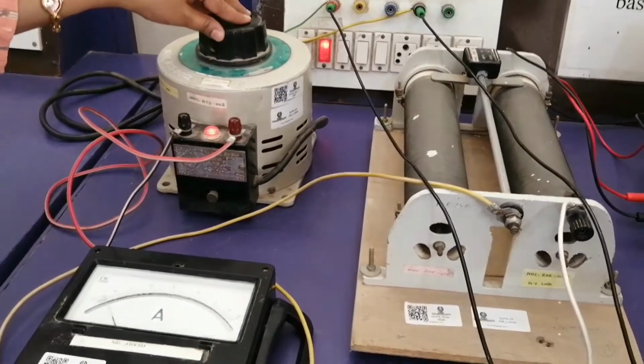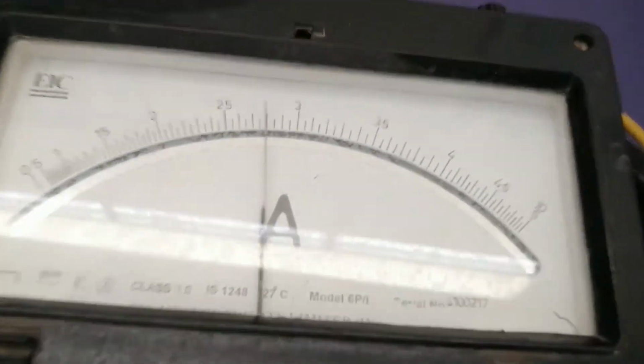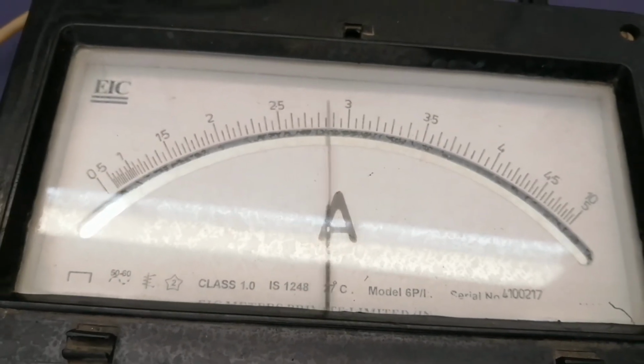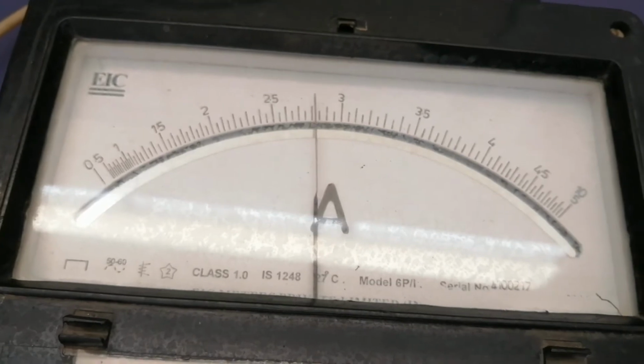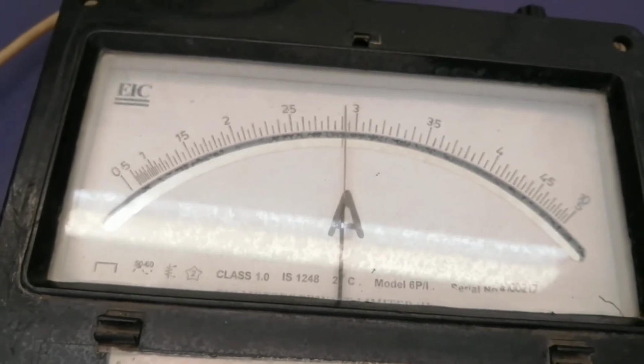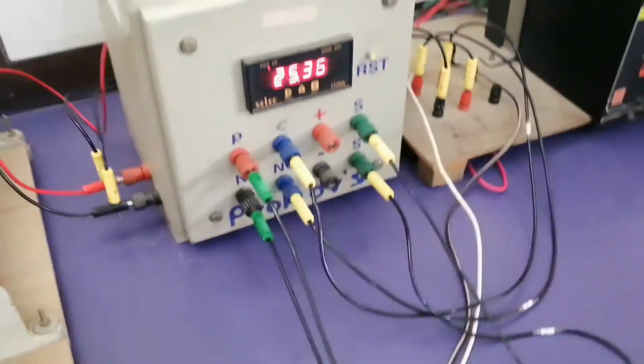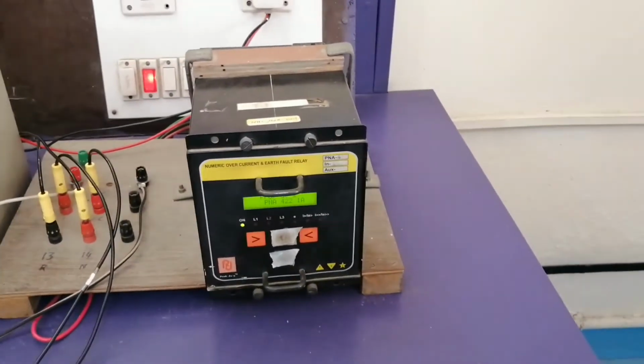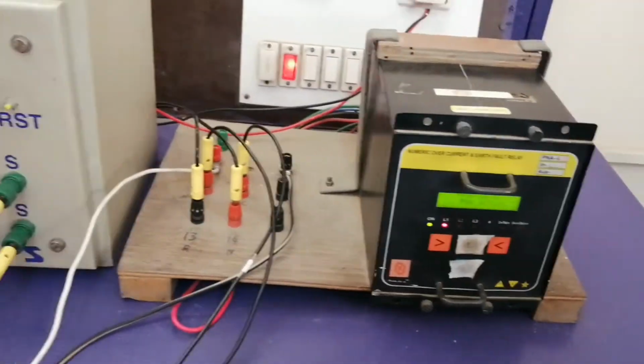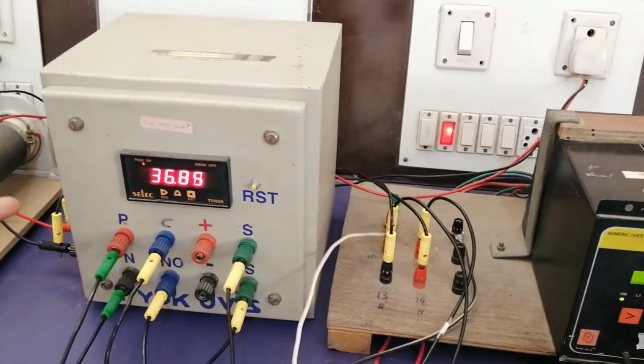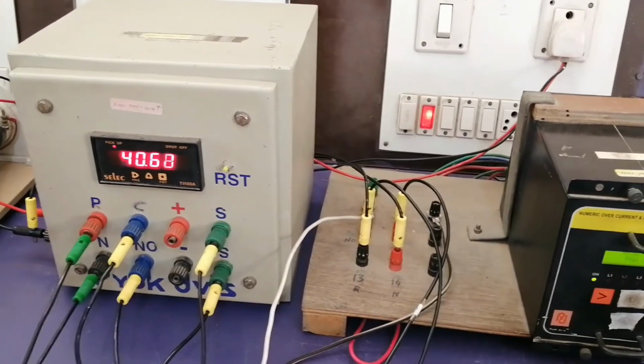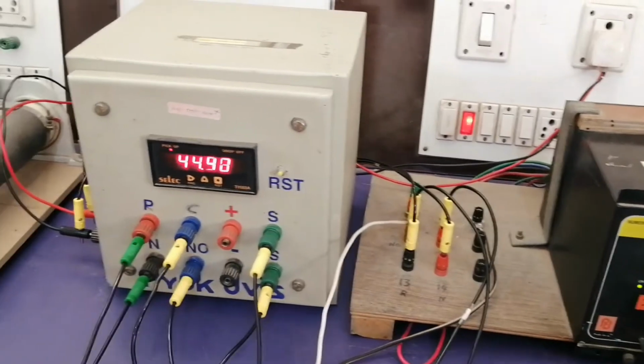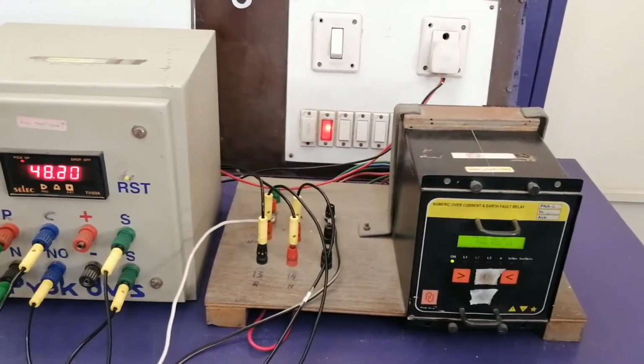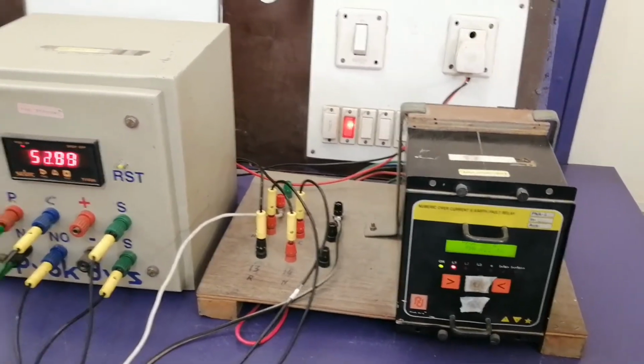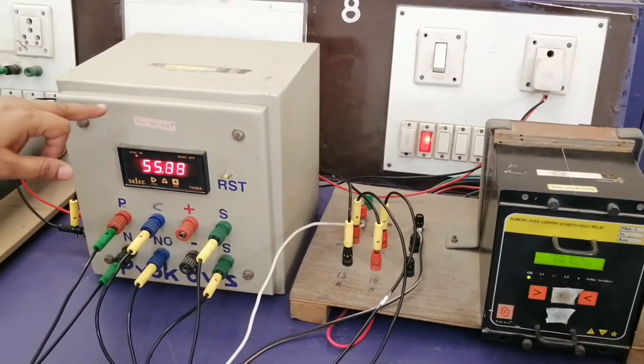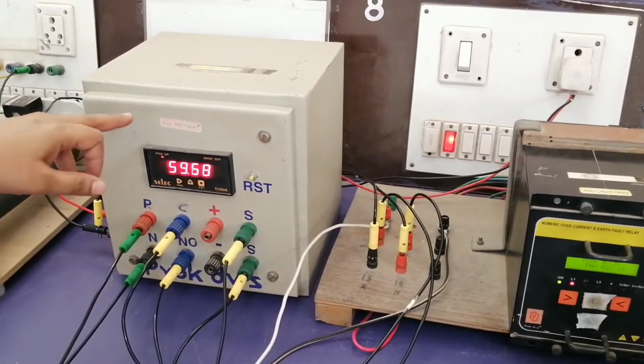So increase the current, make it a fault current of 3 amps. You can see the ammeter reading is 3 amps. When the ammeter reading is 3 amps, you can see the relay box started glowing with L1. But what happens to the timer is, the timer has started ahead of the fault. So the value which occurs here is not the accurate timing value. Once the fault reaches from the ammeter to the relay box, the timer will be tripped, your relay will be tripped. At this point, the timer should know the exact value at which your current reaches 3 ampere, but this is not the exact value.